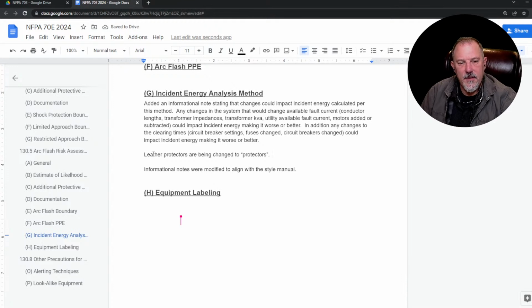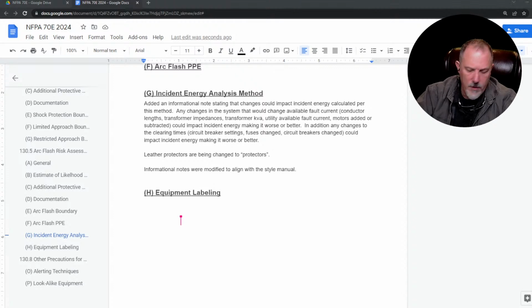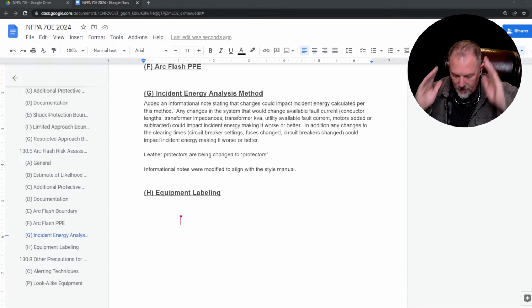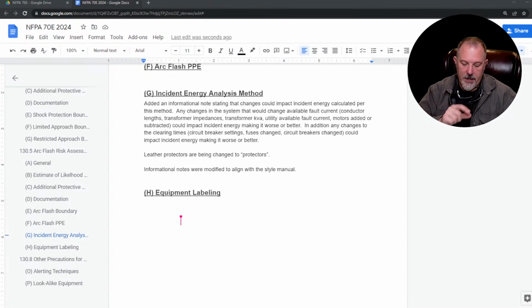So here's the other thing, there's a subtle change. What's the table? 130.5G, is it 130.5G? Yeah, so remember, whenever you calculate incident energy, the next step is you need to determine your personal protective equipment. And you can't use the table in 130.7(C)(15)(c) that has the arc flash PPE categories 1, 2, 3, and 4, because that's only when you're using the PPE category method. If you're calculating incident energy to determine your PPE, you need to use table 130.5G.